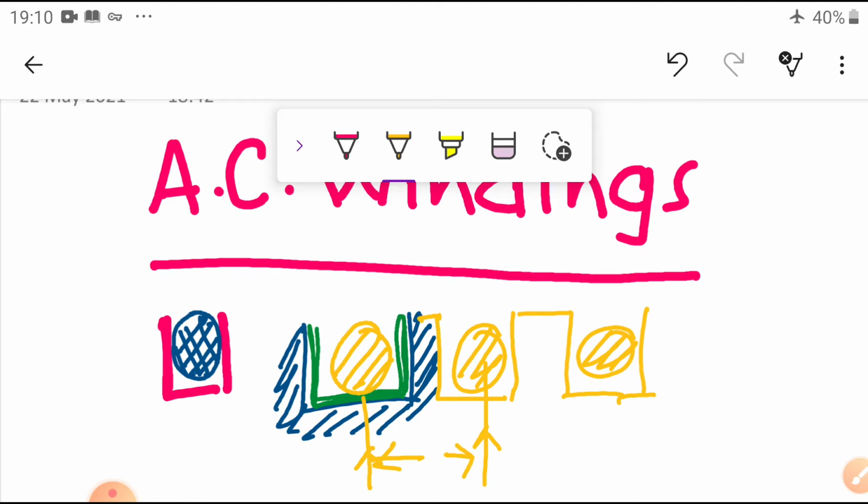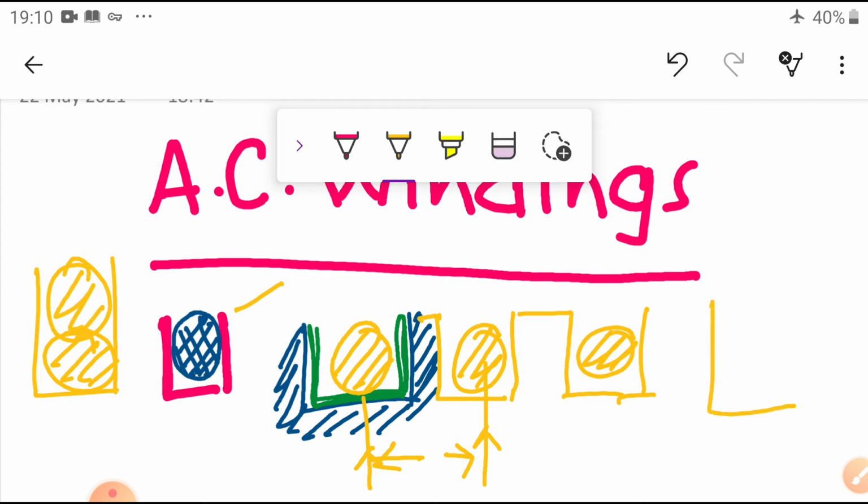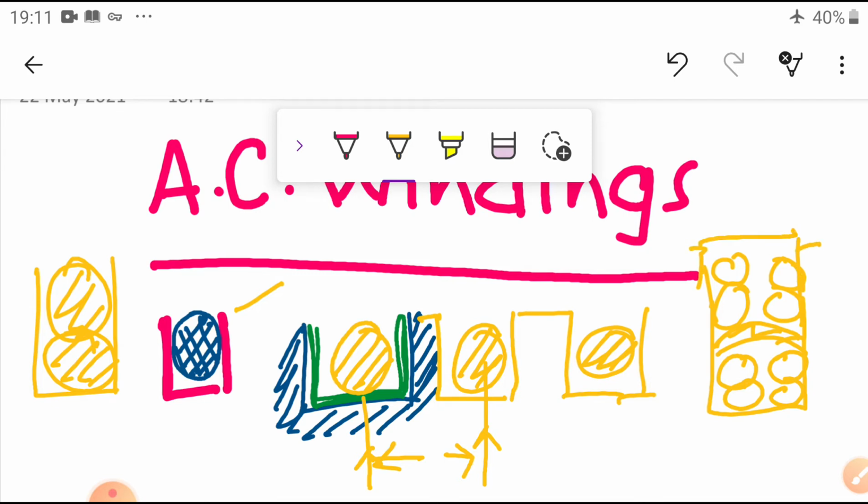Okay, so whether it is a single layer or sometimes we can use a double layer. This coil side, this coil side. Sometimes we can use different layers also. For example, 4 conductors form one coil, there is insulation, and another 4 conductors form another coil. After this we provide some wedge, some wooden stick, placed here, some insulated material. So this is a double layer winding.